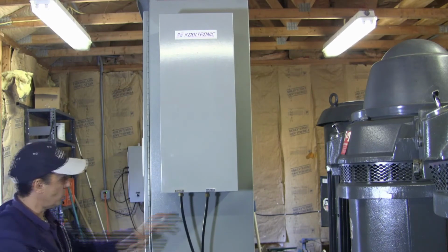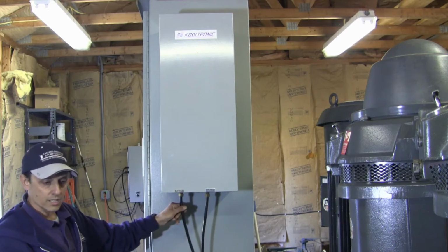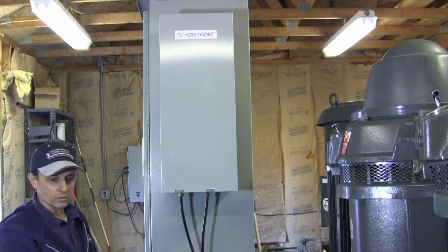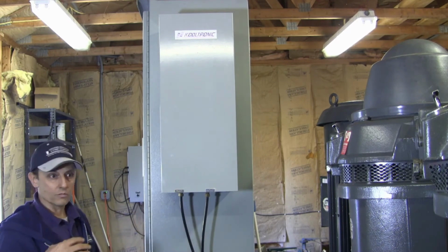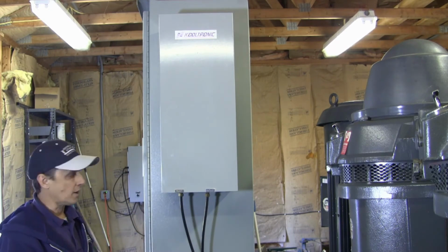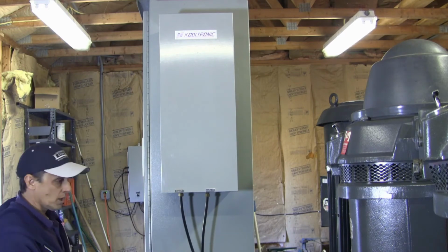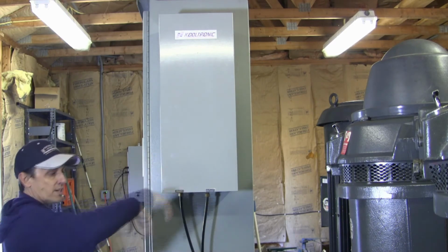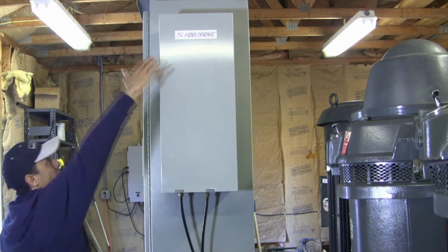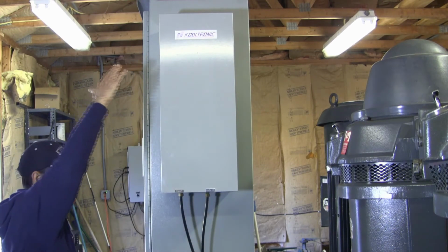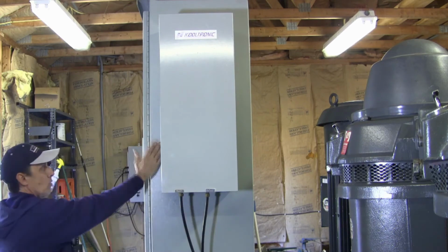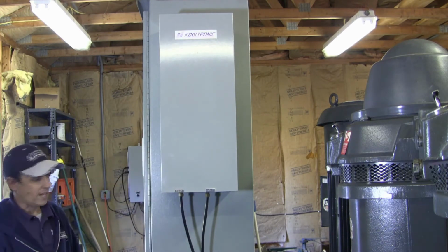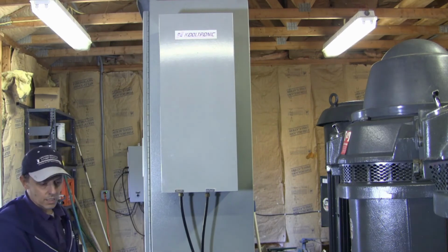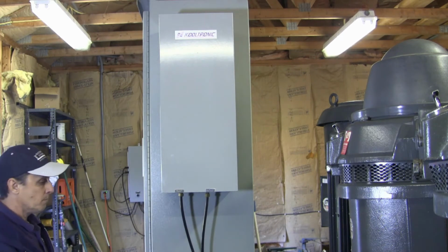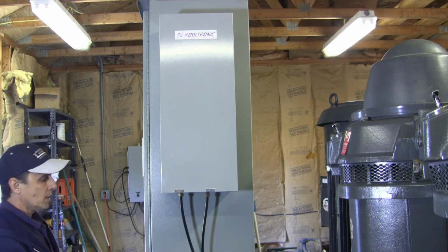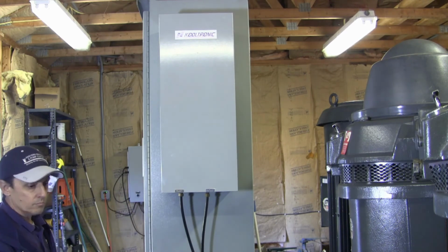There's another style which will have a solenoid mounted underneath the heat exchanger, which will need an electrical signal to turn on and off, and usually that's when the VFD pump comes on. So I guess the whole idea is there's a coil inside of here. The water goes through the coil, and on top of the heat exchanger is a fan, and that fan blows the cold air through a hole in the side of the panel and cools off the panel. A lot of times we'll get calls about stations shutting down.